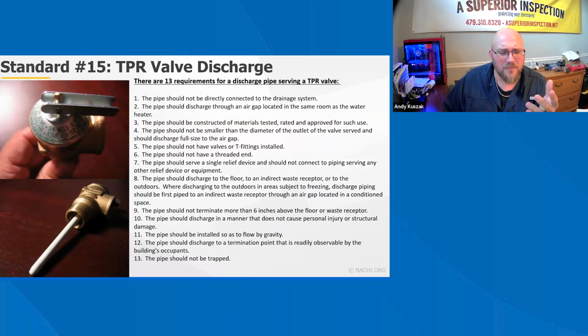So anyway, a lot of times you'll see reductions, installed by a plumber, where they take a very small copper pipe, probably 3/4 inch maybe, and put an adapter on it and attach it to the end of the TPR valve. And I find this all over my area in existing 1980s homes and older. I always call that out. And I'm probably getting ahead of myself, but if there's a crawl space, a lot of times that pipe just goes through the floor and disappears into the nether. So 3/4 inch. Thank you, Rick. Appreciate you. So anyway, 3/4 inch on the sides, but they'll put a 1/4 inch pipe and adapter on top of it.